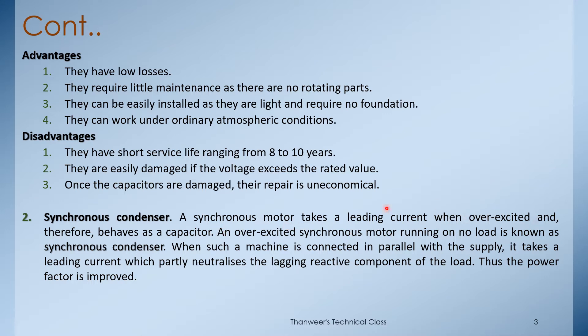Synchronous condensers: a synchronous motor takes a leading current when overexcited. A synchronous motor running on no load is called a synchronous condenser. When such a machine is connected in parallel with the supply, it takes a leading current which partly improves the power factor.